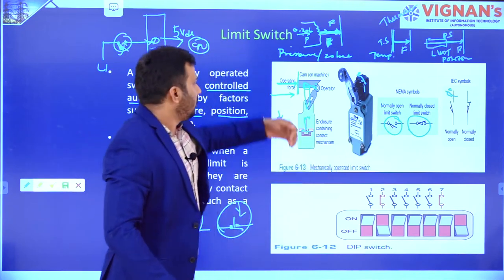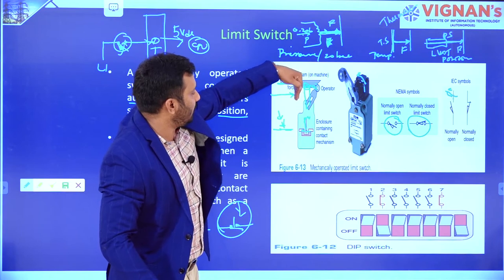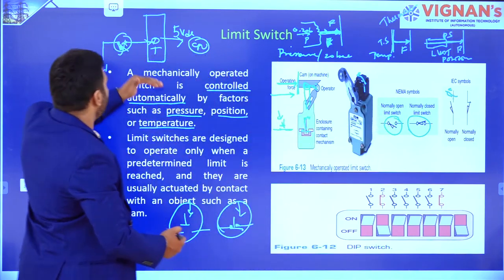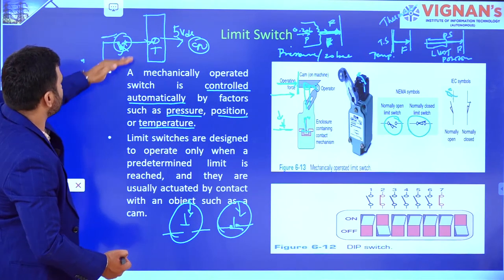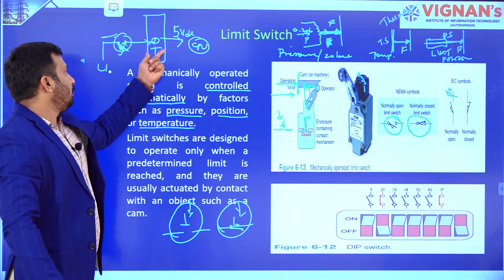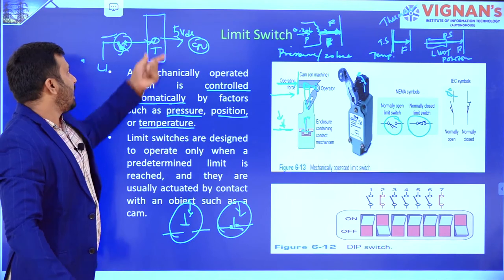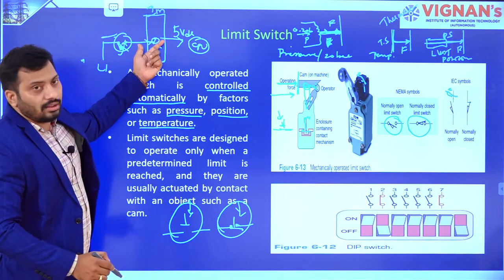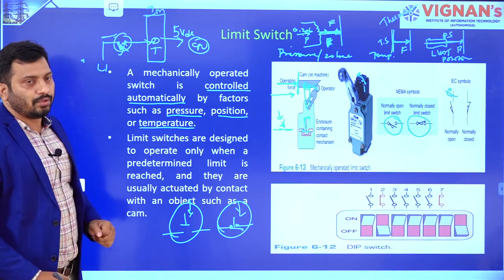For example, if it is normally open type, whenever this crosses the limit, what will happen? This is going to be a closed contact. Previously we discussed — whenever the limit switch is closed, what will happen? Line voltage acts as input to the terminal. Whenever the input signal comes as input to the IO module, this IO module will perform internal signal conditioning, and 5 volts DC is going to be given as output.